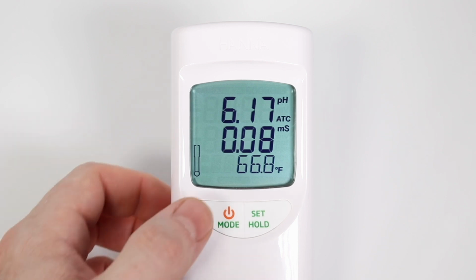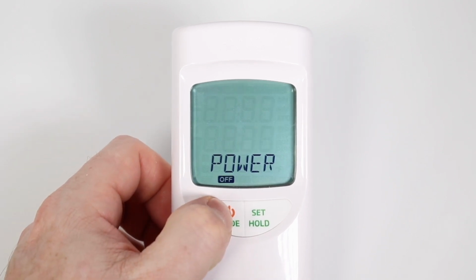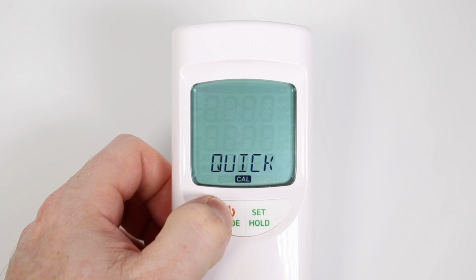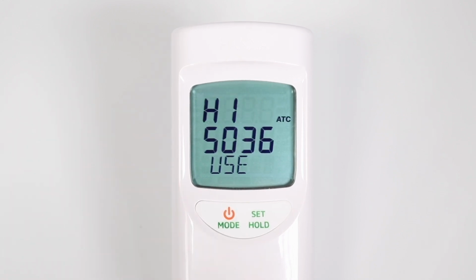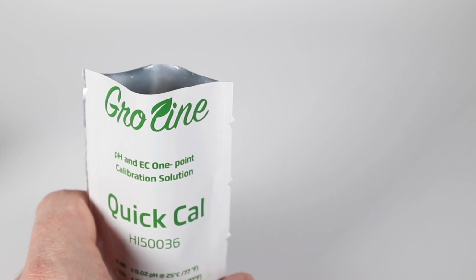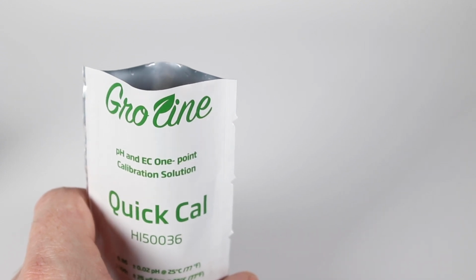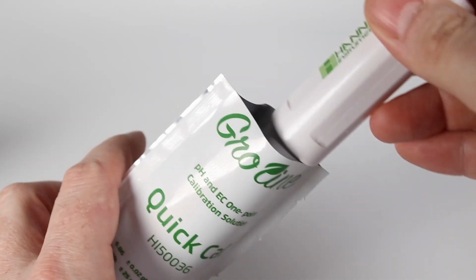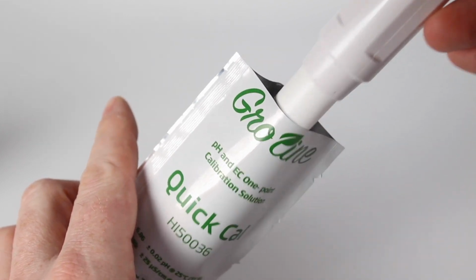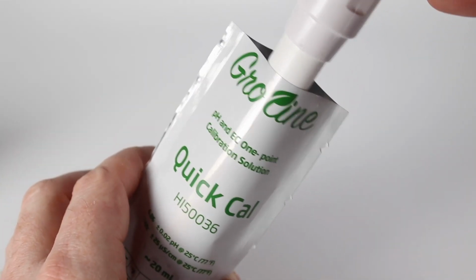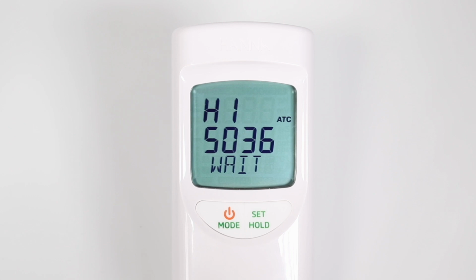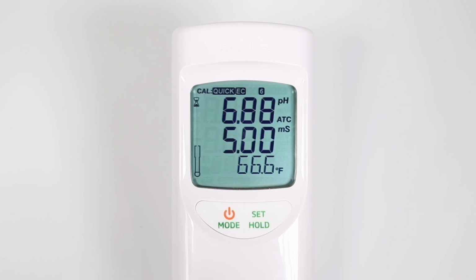Press and hold the mode power button until Quick Cal appears on the screen. Release the button and HI50036 Use will appear on the screen. Immerse your probe into the solution, inserting the probe with a slot facing upward to help release any air bubbles. Tilting the packet at a 45-degree angle ensures that the entire glass bulb is covered with solution. Wait until Save appears on the screen. Your meter is now calibrated and will return to the measurement mode. You do not need to press anything to save the calibration.